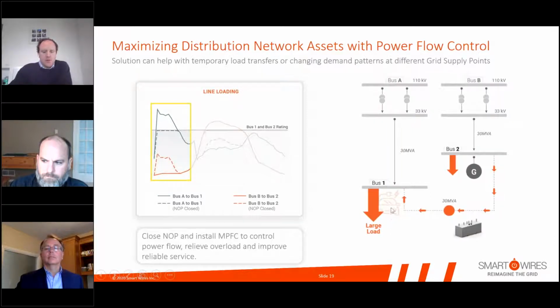By closing up the normally open point, you can actually feed this load through two buses rather than one, and use power flow control to make sure that those thermal limits are maintained on all circuits. So you're bringing your overloaded thermal loading on that line back down to within the line rating.